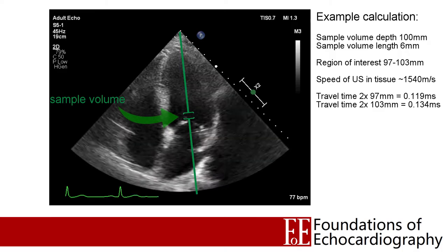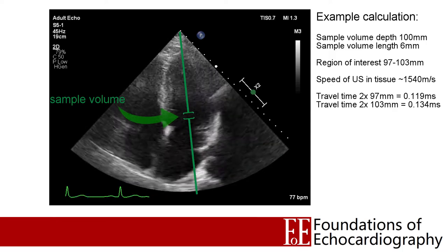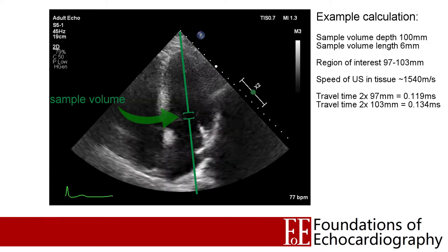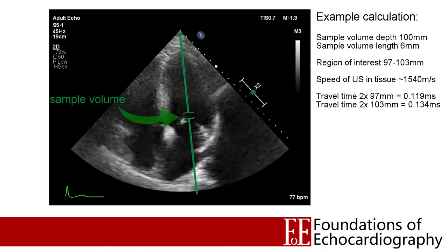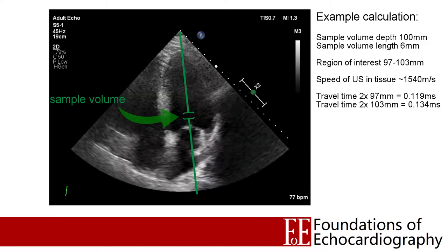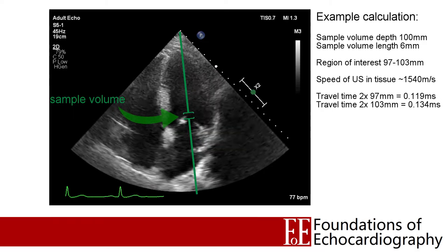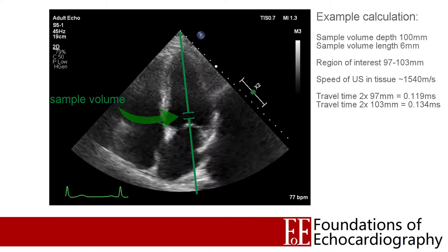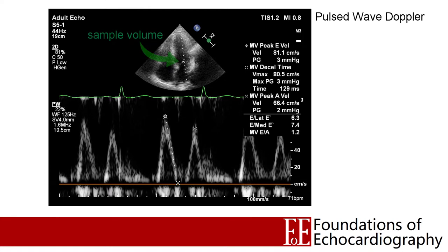The ultrasound software knows that if it sends out a pulse of ultrasound and it returns before 119 microseconds, then it won't have had time to reach the sample volume and return. Likewise any signal returning later than 134 microseconds would have been reflected from a structure deeper than the sample volume. It knows to ignore all information returning outside of that gate, and only tell us about information that arrives between 119 and 134 microseconds after the pulse was emitted. By sending several thousand pulses of ultrasound along this single scan line each second, the ultrasound software is able to measure the shift in phase between the transmitted and received waves, then use the Doppler equation to calculate the velocity.